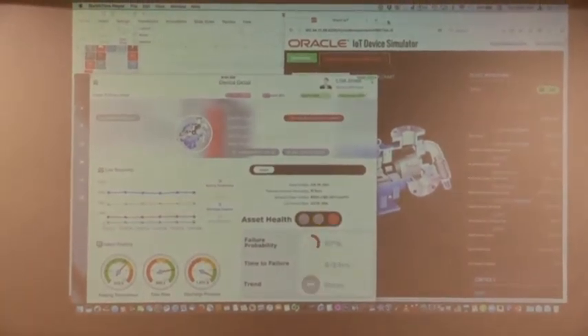You all of a sudden see the asset health turn from green to amber to red. This is the real-time predictive algorithm detecting the issue. Now, do you see the range of the pump values? The range is still in the green for all the parameters we're checking - bearing temperature, flow rate, discharge pressure. It's still in the acceptable range individually, but a combination of all of that is causing the pump to fail.